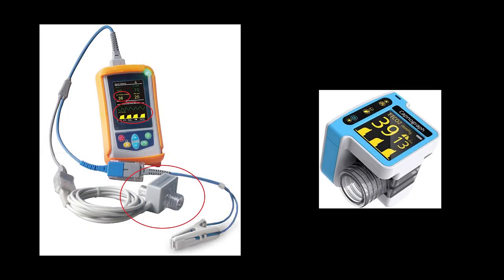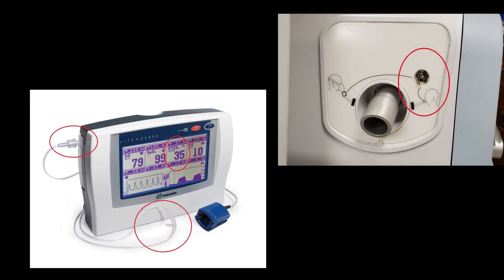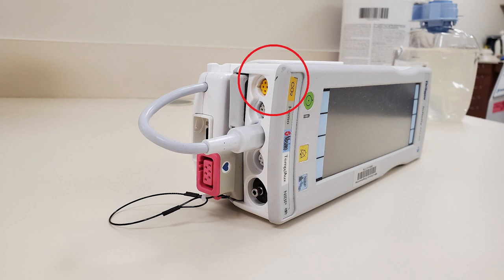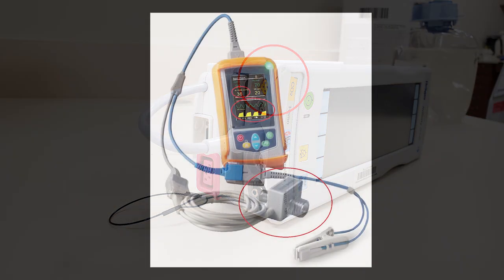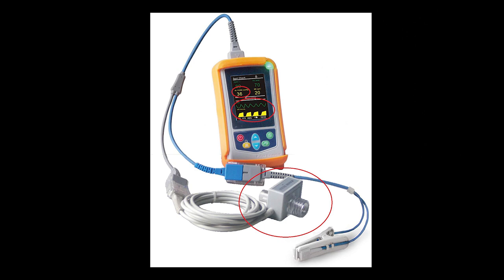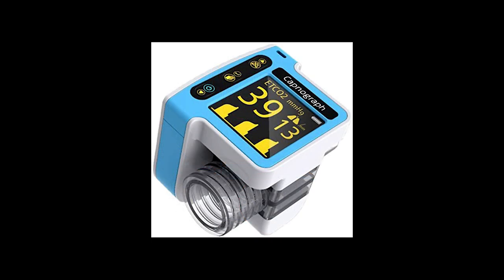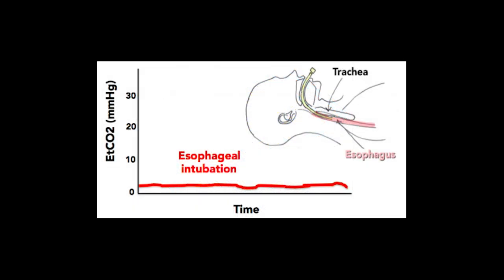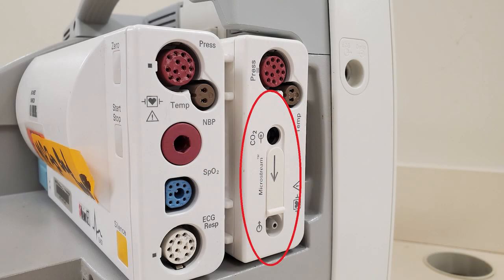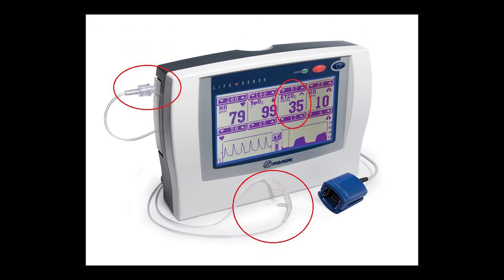There are two types of end-tidal sensors: mainstream sensors and sidestream sensors. Mainstream sensors take measurements directly at the main tube connected to the patient. There's no delay in the results, as the electrical components are located immediately at the source. This type of EtCO2 monitor is often found in areas where the patient is intubated, like operating rooms, ICUs, and the ER sometimes.